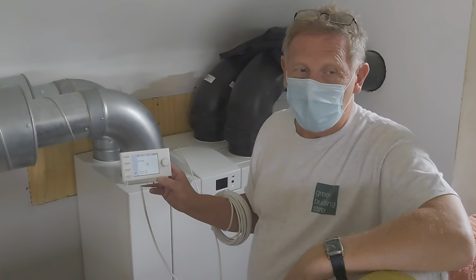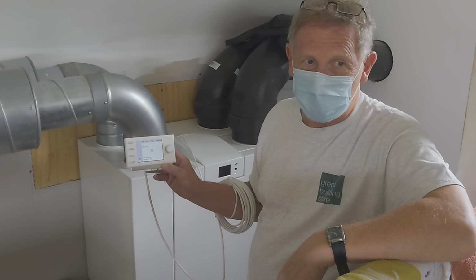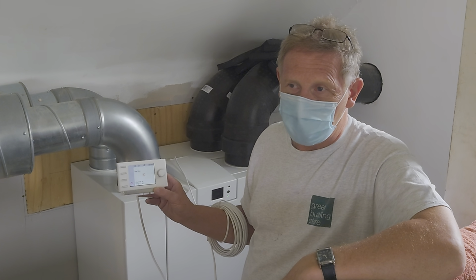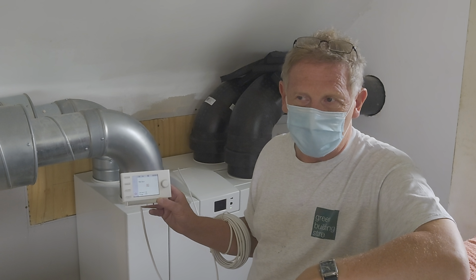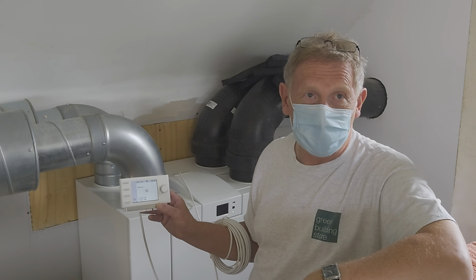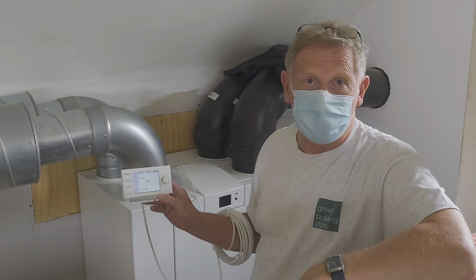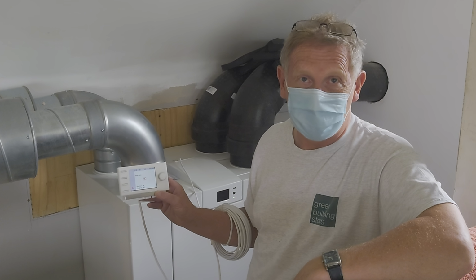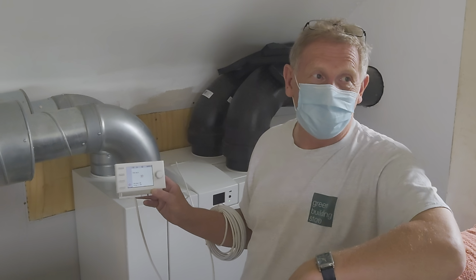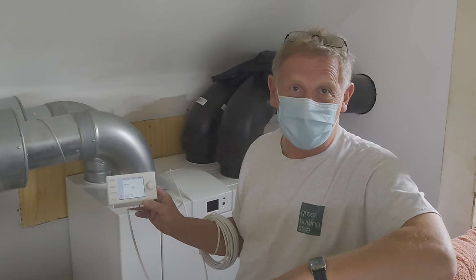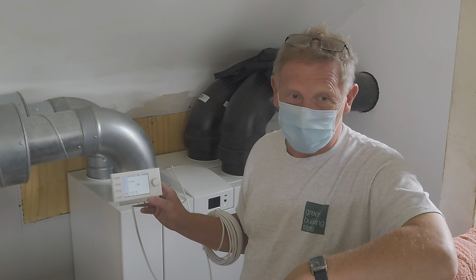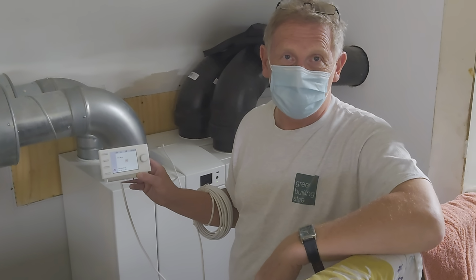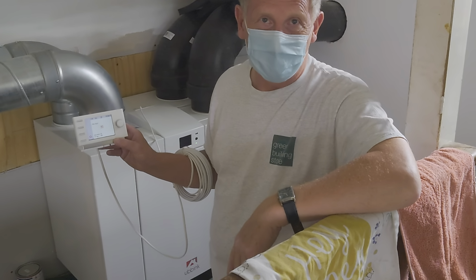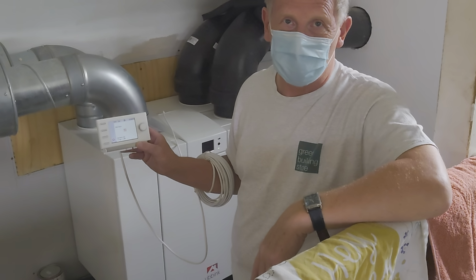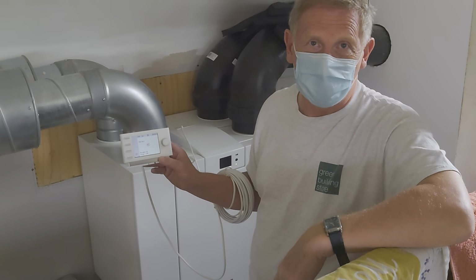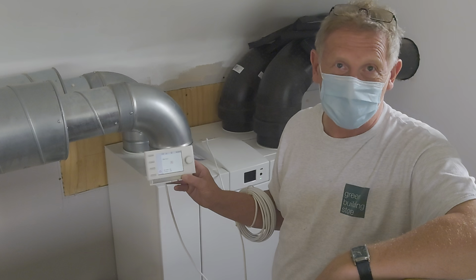And you replaced it because of new efficient ones on the market? I replaced it because after only about 8 to 10 years they stopped making the machine and stopped making the filters, so I was having to make my own filters, not very successfully as it turned out, dust had got through them. And after 20-odd years the heat exchanger wasn't clogged up with dust, but it had dust inside it, so it wasn't running very efficiently. It was never a very efficient unit in the first place.